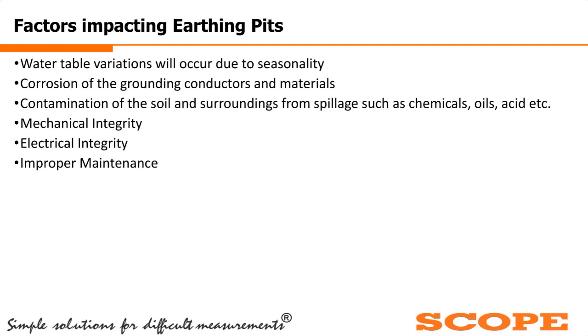Then next we will see the different factors affecting the earthing pits. Generally, the earthing pit's performance is affected by water table variations. Let us consider the summer season: the water levels are not that high, because the earth surface nearby the earth pits has very little moisture content. Due to that, the earth resistance varies because of the lower moisture ingress in the soil. And in rainy seasons the water levels in the soil increase, so the effective earth resistance is reduced. So this depends upon the different seasons. The water table variations cause a change in the performance of the earth pits.